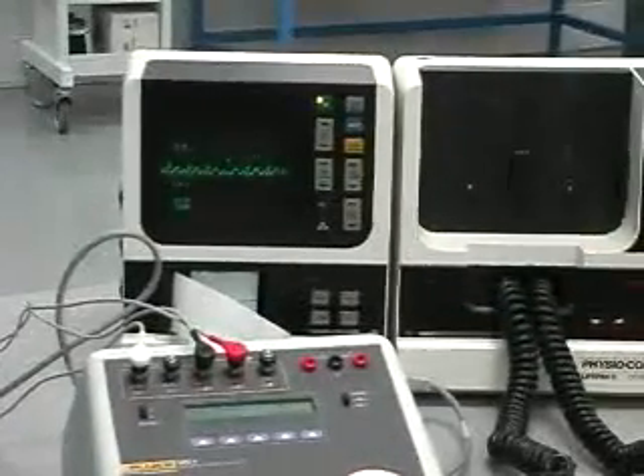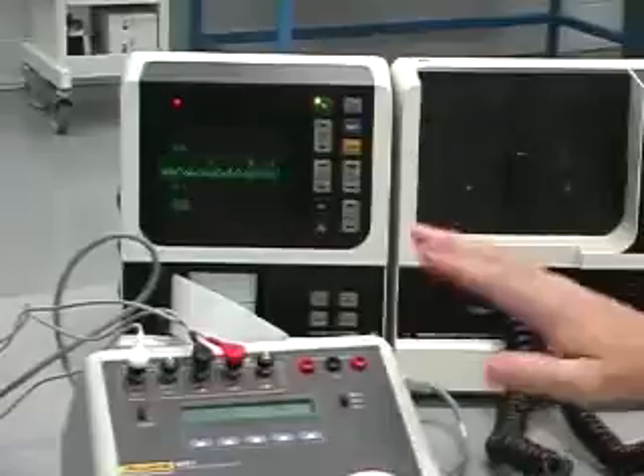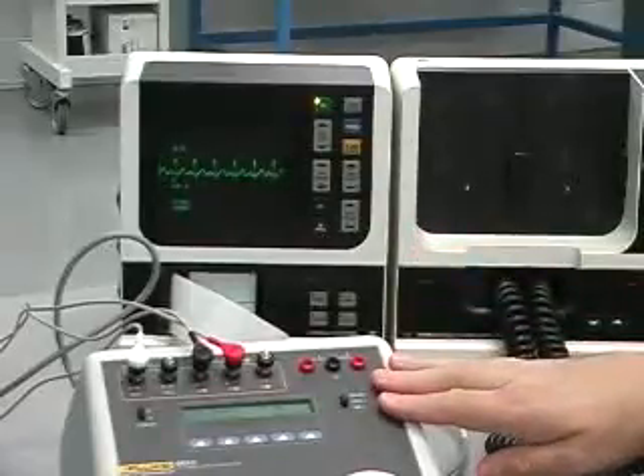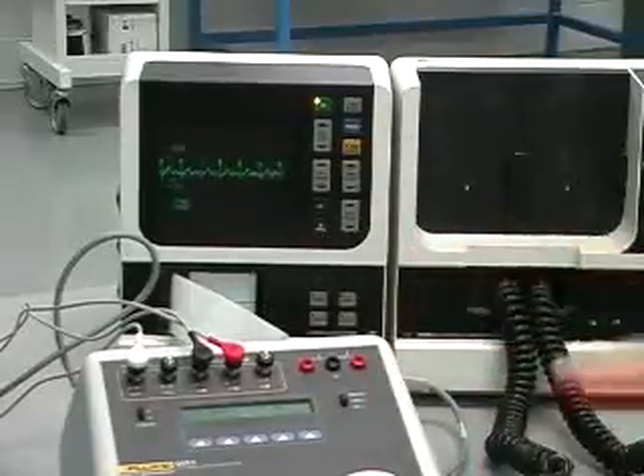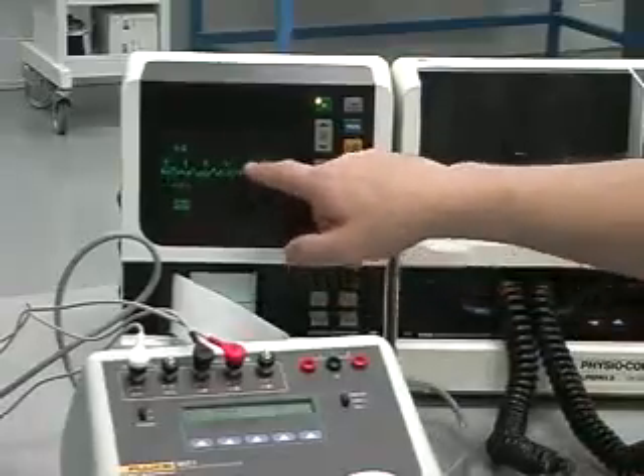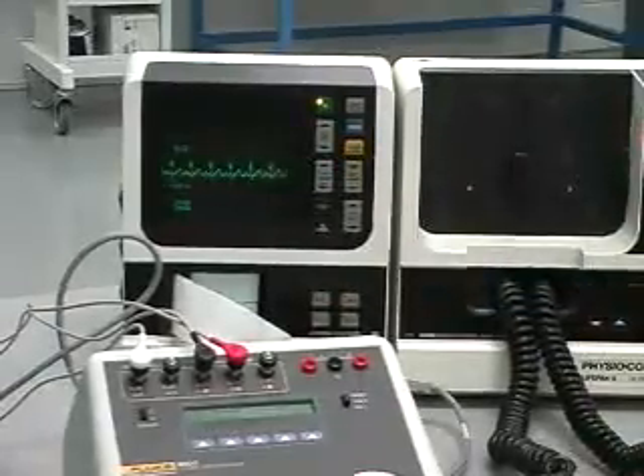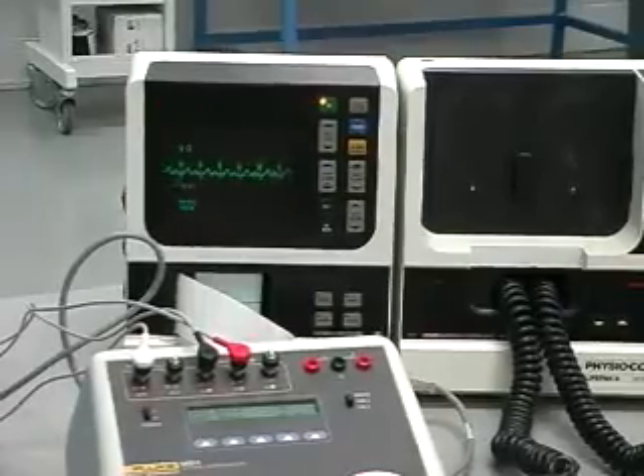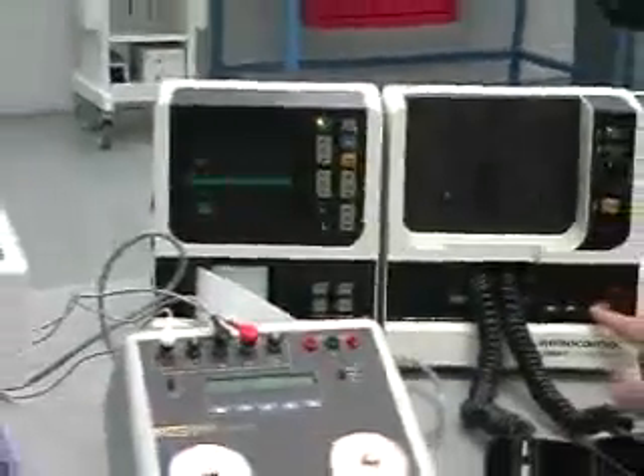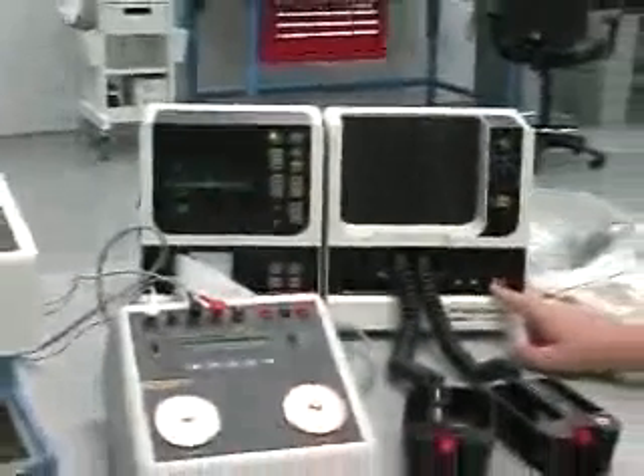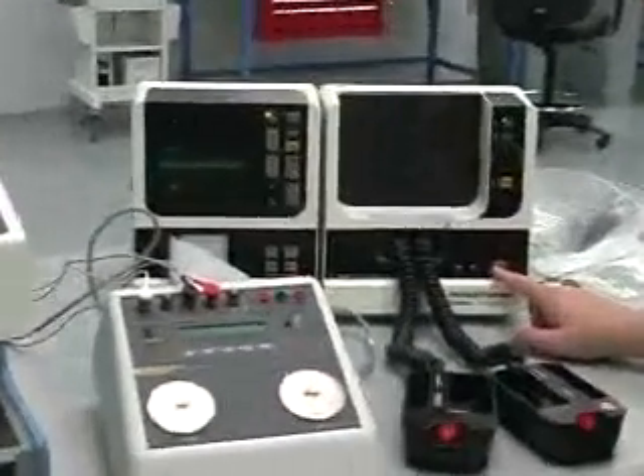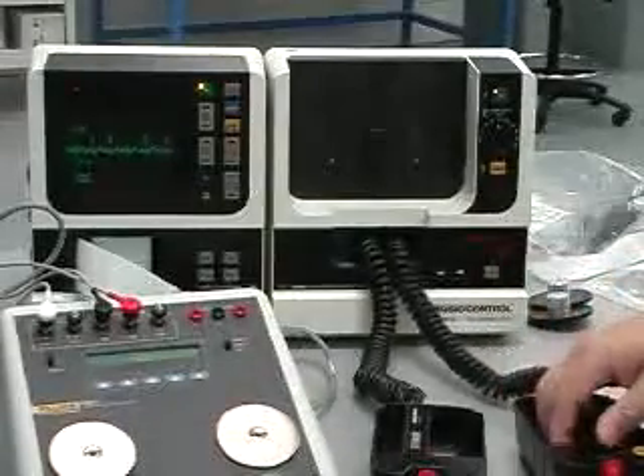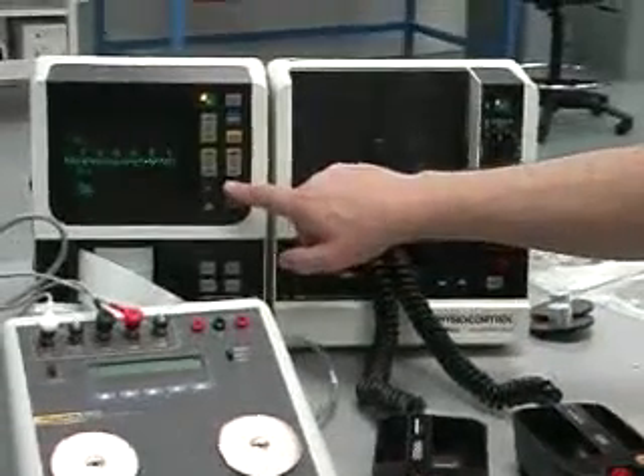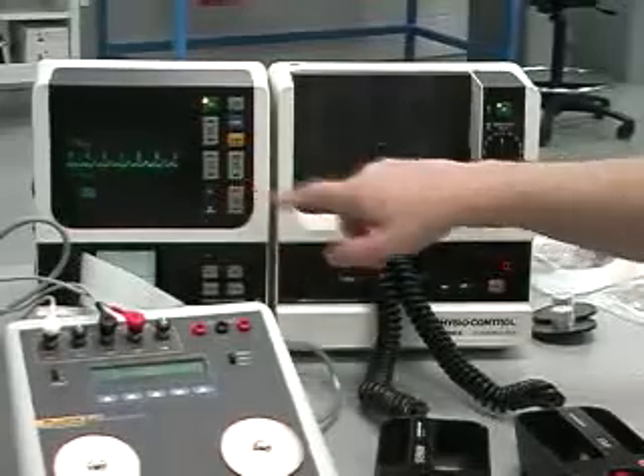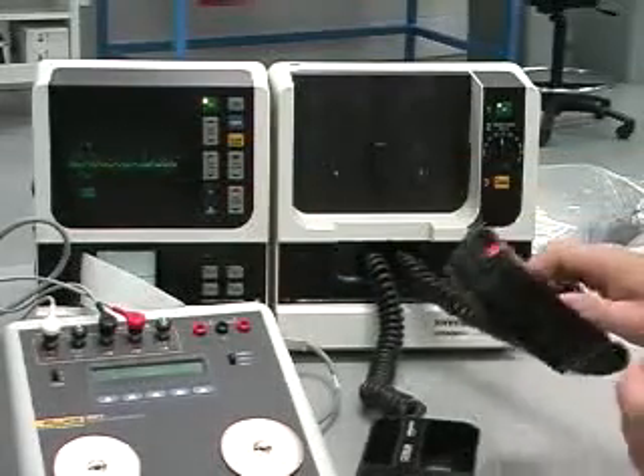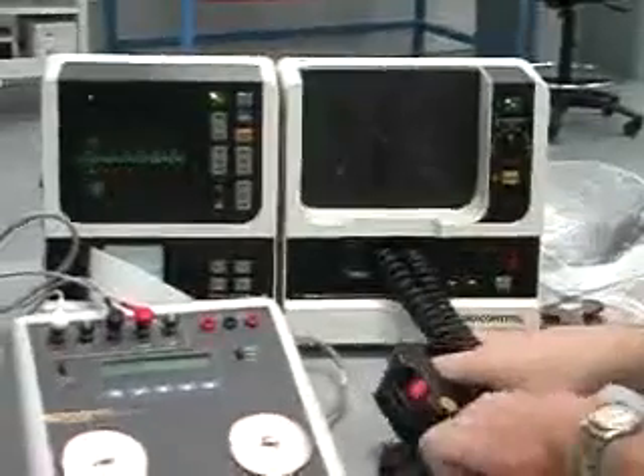So at this point, the defib will only discharge when the buttons are pushed and one of those markers has come through, and it does sense that ECG. So the sync light is illuminating and flashing at the ECG rate. So just to make it a little easier, the defib should discharge when you hear one of those beeps.